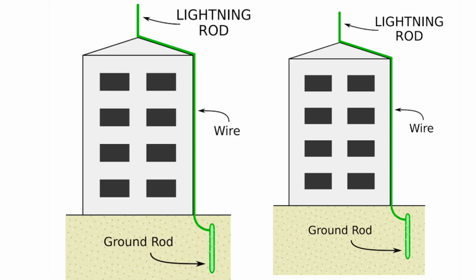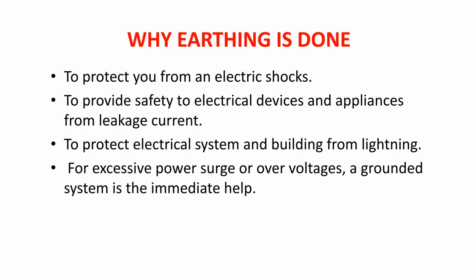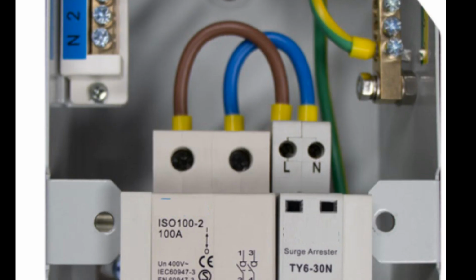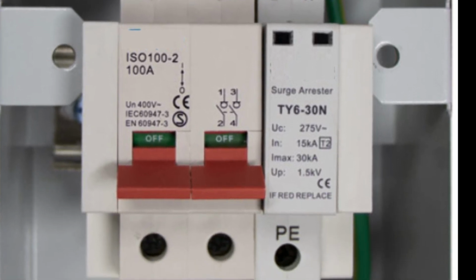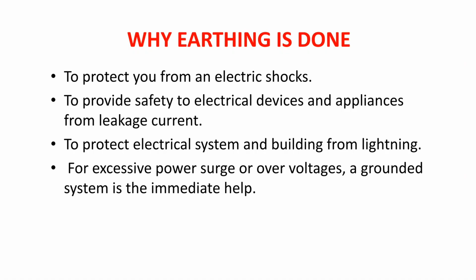Next, it protects your electrical system or building from lightning. For this purpose we also require a lightning arrestor, and earthing is connected to the lightning arrestor. So whenever lightning occurs, the lightning arrestor catches it, and through earthing it is discharged to earth. And the next one: for excessive power surges or over voltages, a ground system is immediate help. If our electrical system does not have surge protection devices or other things, the immediate help will be given by earthing. In my last videos related to SPD, I have already told you that SPD requires earthing, or SPD remains connected to earthing from one end. So friends, see how important earthing is to protect you and your electrical devices from high currents, leakage currents, etc.